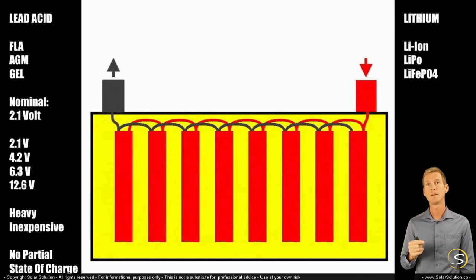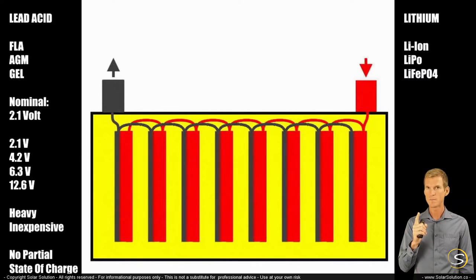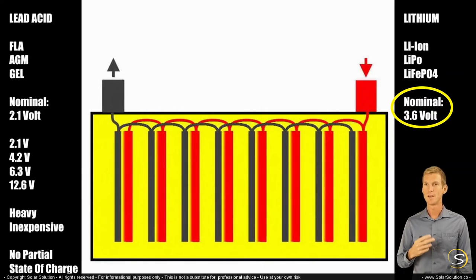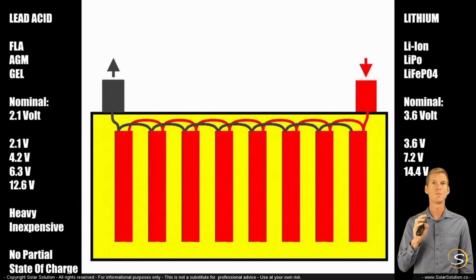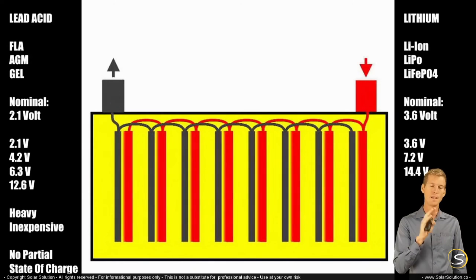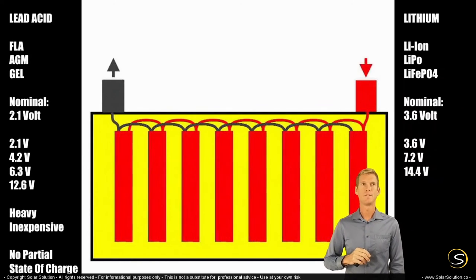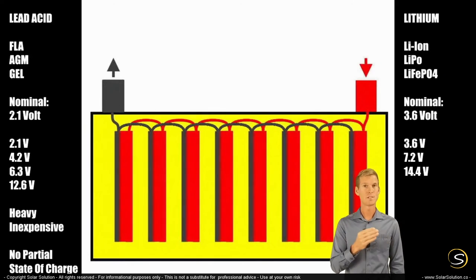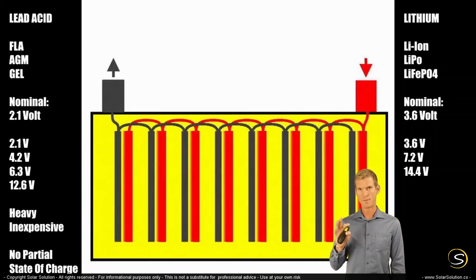An important difference between lithium and lead batteries is that their nominal voltage is different — substantially higher. The nominal voltage of one lithium cell is generally 3.6 volts. Combining multiple cells in series: two cells give 7.2 volts and four cells give 14.4 volts. This 14.4 volts is in a similar range to the 12.6 volts of a lead-acid battery with six cells, which is why they can often be used interchangeably. Typically, 12-volt nominal lithium-based batteries have a slightly higher voltage than lead-acid-based batteries.